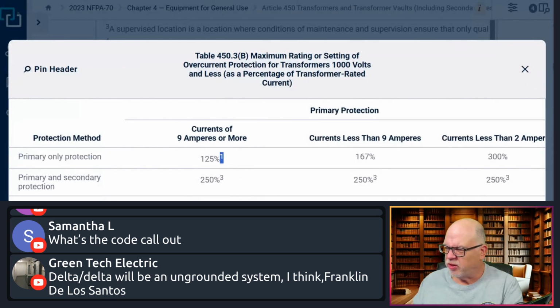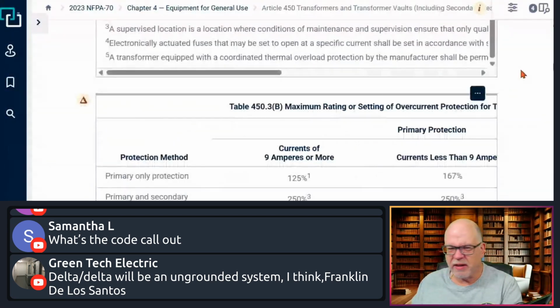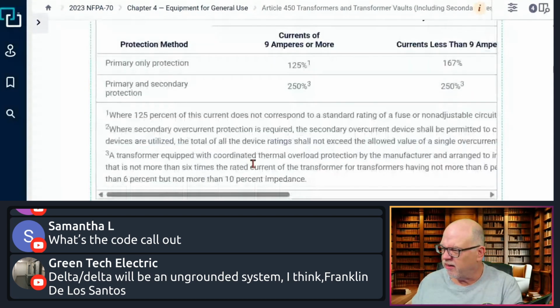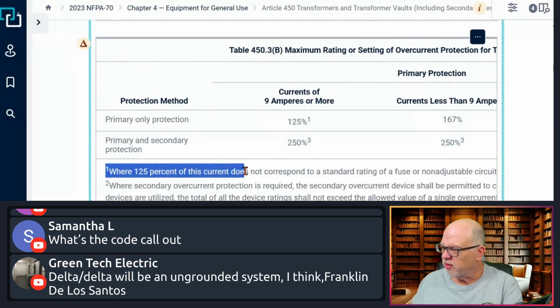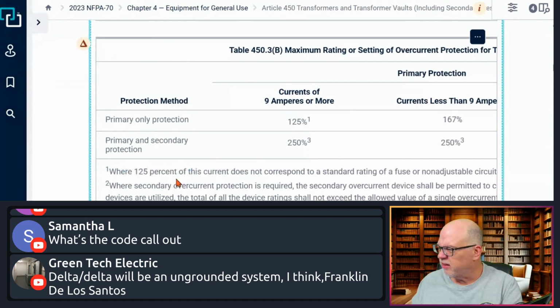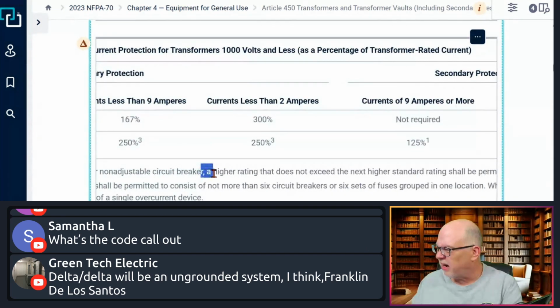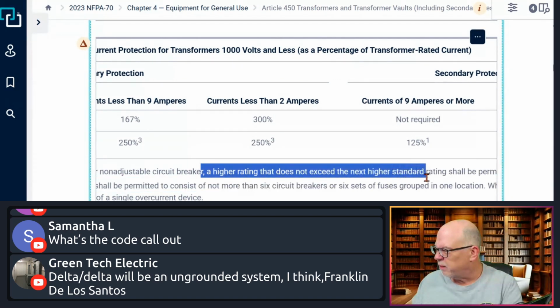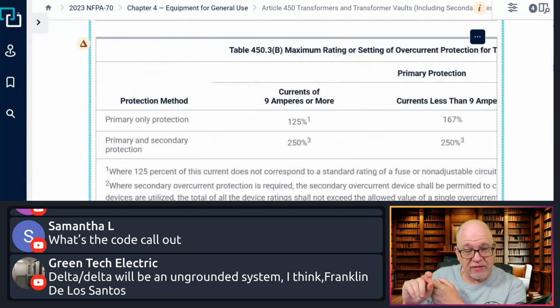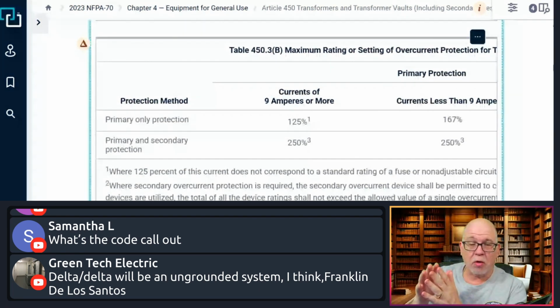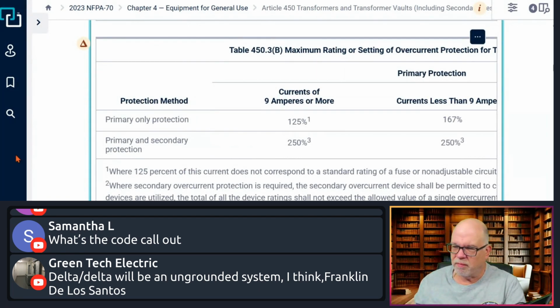And this 1 is a footnote that puts you down here. It's not letting me scroll down that far, so I'm going to shut it down and give you the screen so you can see it. Right here. Here's the note: where the 125% of the current does not correspond to the standard rating of the fuse or non-adjustable circuit breaker, the next higher standard rating shall be permitted. And again, y'all know that we go to 240.6 to find the standard overcurrent protective device ratings. So that allows me to do that.